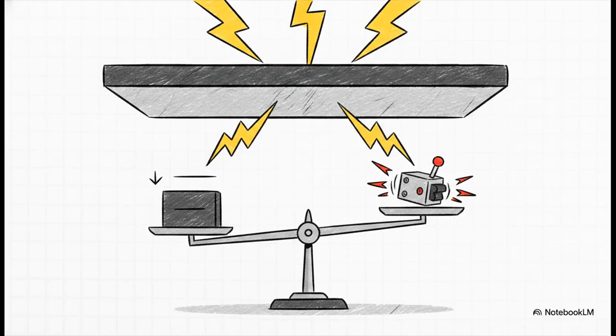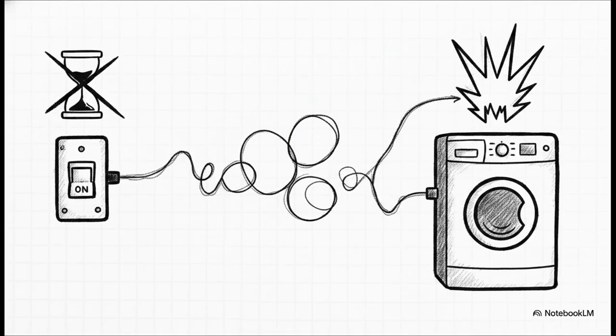So to completely prevent a delayed trip, Clause 5.7.4 gives us a strict mathematical ceiling on resistance. And this brilliantly illustrates how math essentially guarantees human safety. The formula is the impedance of the loop, Zs, multiplied by the tripping current of the breaker, Ia, must be less than or equal to the system voltage, Uo. Let's break down these variables just a bit more so we can see how they interact in the real world. As we just said, Zs is the total impedance or resistance of our giant fault loop. Ia is the specific amount of current required to force your specific circuit breaker to trip instantly. And Uo is the nominal voltage of the system pushing all that current through.